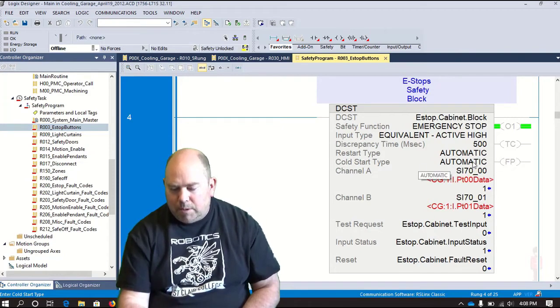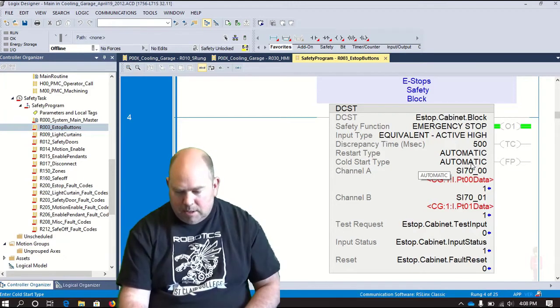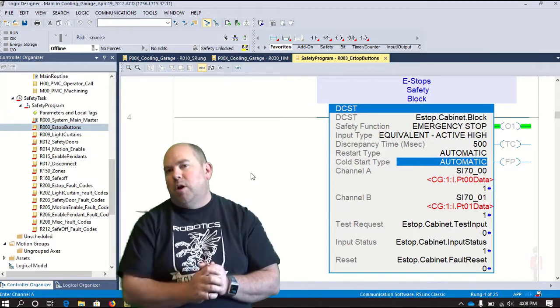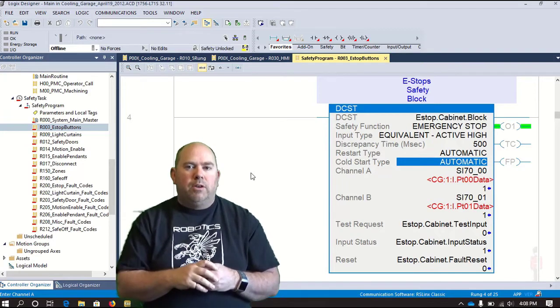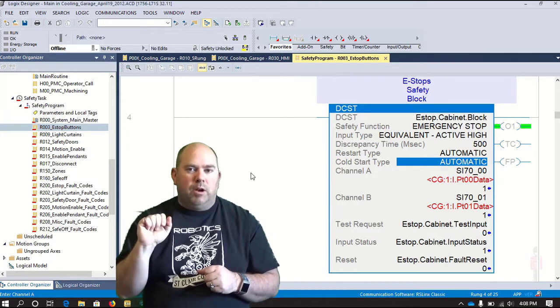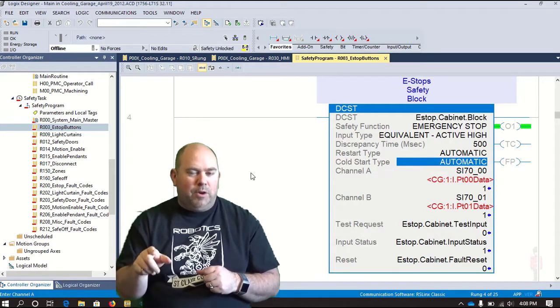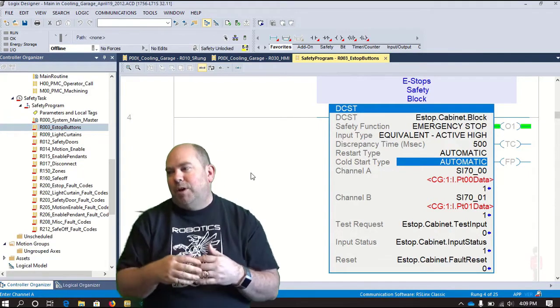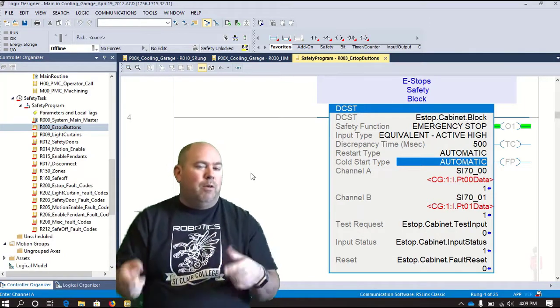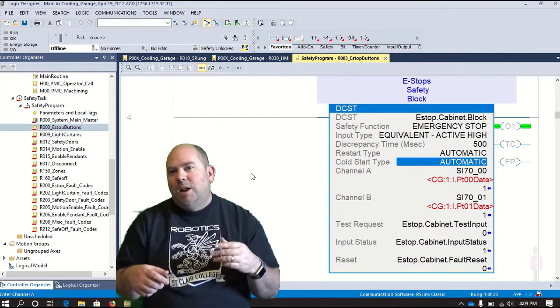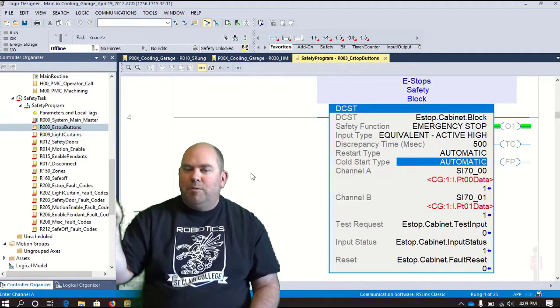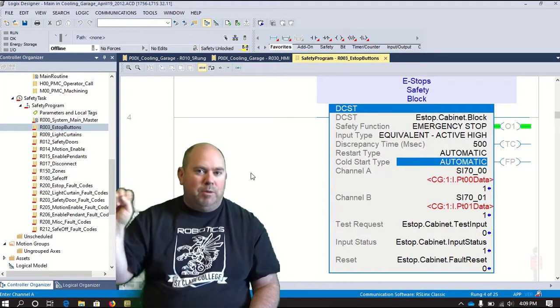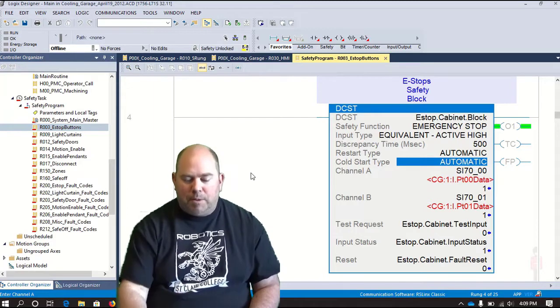The cold start type is basically the, what do you want to do when the PLC first powers on? Do you want the block to be set and ready to go? Or do you want it to actually have to go around and push the e-stop, pull it back out, and do a reset on it? How do you want it to handle first initial power-up? This is very important when you have a lot of safety gates or something like that. One thing we found, if you have like 100 safety gates on a system, and you download the program, and then, or put the program in program mode, and then come back again. Do you want it to have to go around and actually open and close 100 different safety doors and reset them all? Or do you want them to just say default state is going to be, they're just going to work? So that is the cold start type.